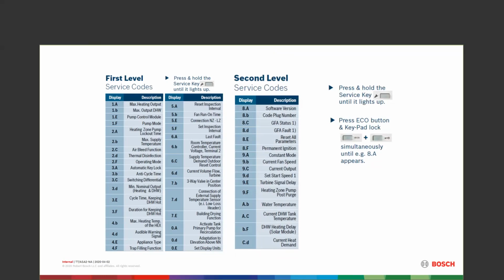So that brings us back to that. 8F is permanent ignition. That just turns the igniter on so you can see what's going on with that. It just stays on the whole time that things are going. You'll be able to hear it, see it, and check out what it's doing. 9A will set it to run constant and just bounce off a limit. 9B is what your current fan speed is. 9C is what your current output is.